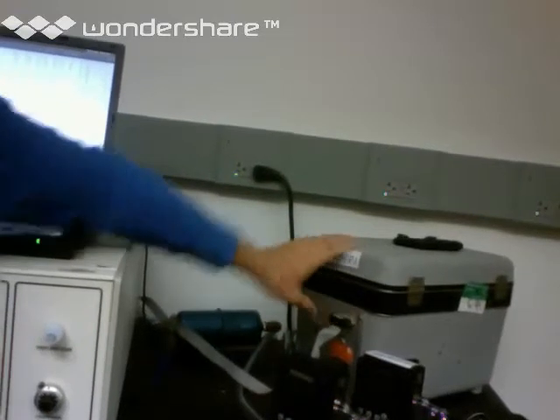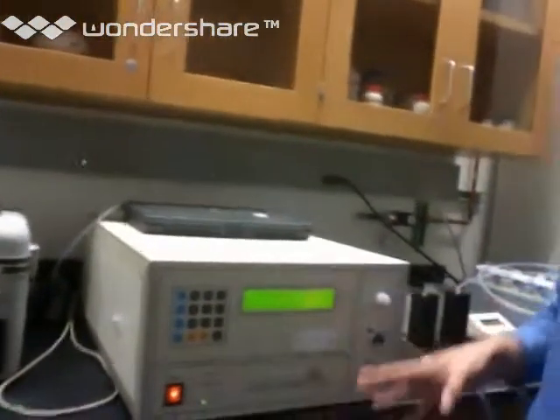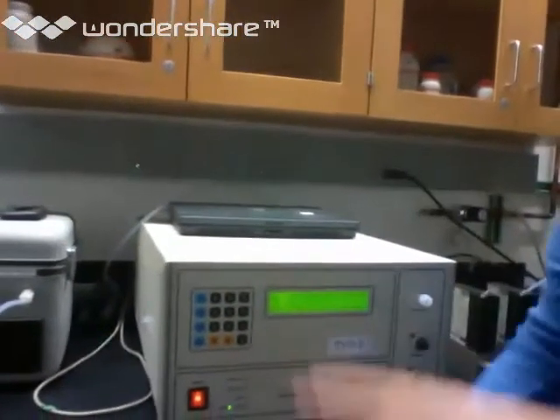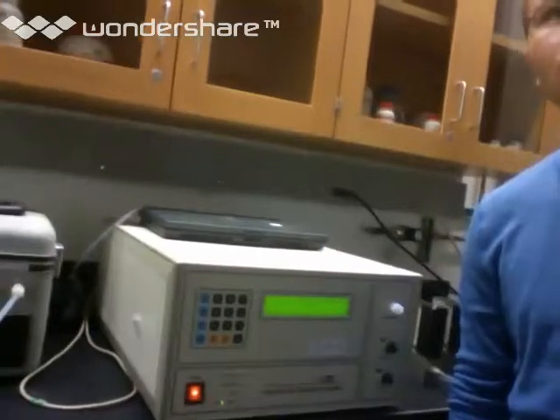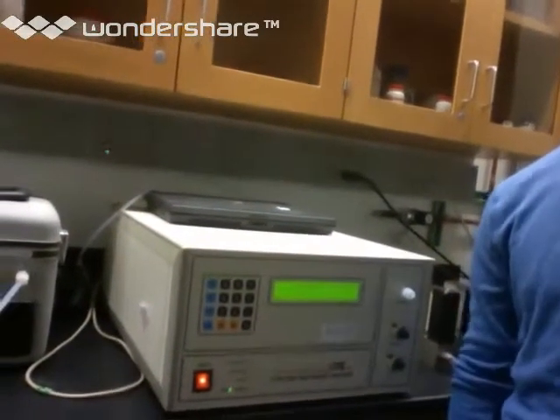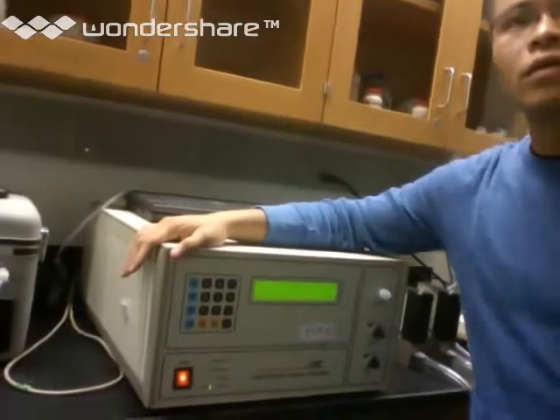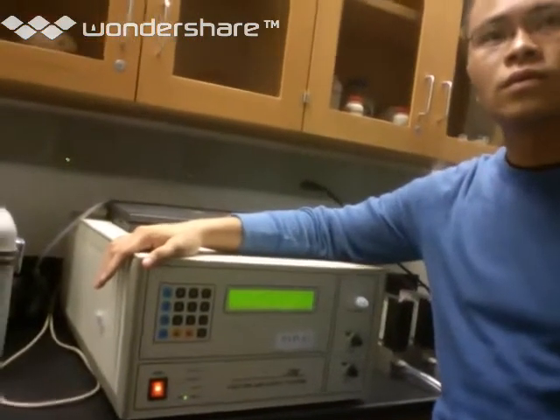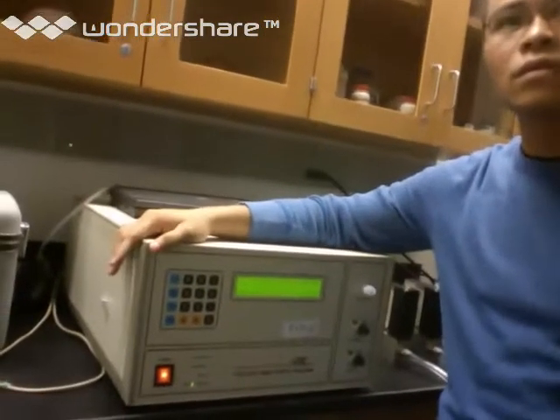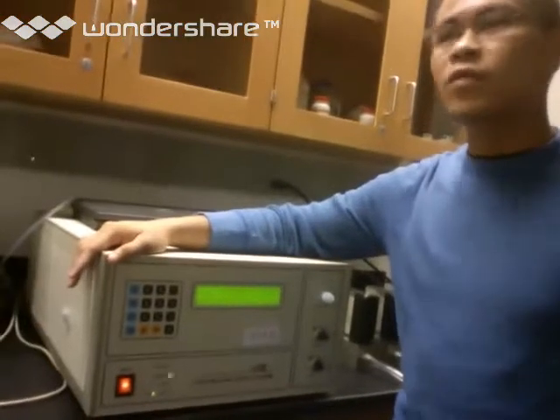I like to turn it on right now because I'm kind of still maintaining these things. So I want to make sure the ribbon cables are working, and I'm still diagnosing those problems. That being the case, I just turn the zero air on just in case, because for a calibration, obviously, you'd want it to be on. Otherwise, in any other situation, normal operation, you don't need to turn it on. You could leave it in auto. Okay, so it's currently in manual mode right now. Yes, it's currently on manual. Yeah. Okay, so with that, you have to be aware when to cut the zero air on. Yeah. Okay. And so when do you typically cut the zero air on? Before I inject it in a calibration. Okay. If it's during a run, generally you don't need to because it'll sample from the proper port itself.